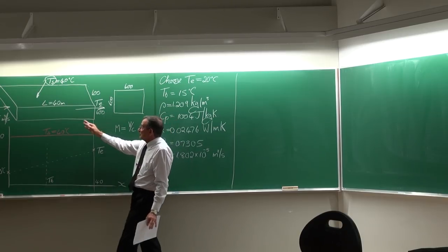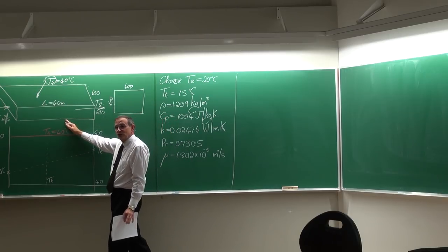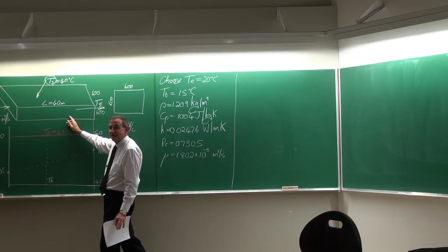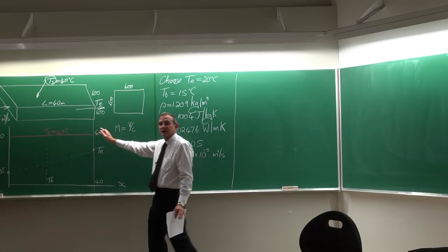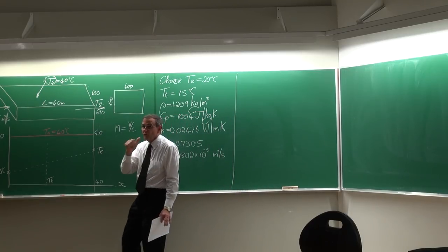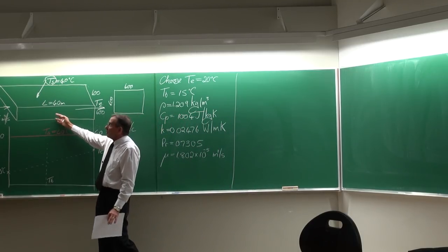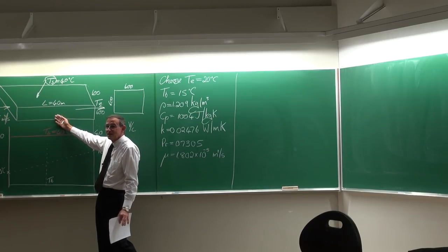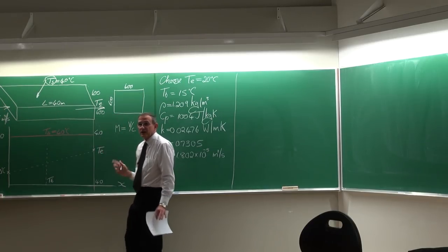Now, I promise you, if you've got a velocity inside an air conditioning tube of 100 meters per second, everybody will run away. It's extremely noisy. I think a rule of thumb is that your velocities are typically less than 10 meters per second, order of magnitude. So it's very low.